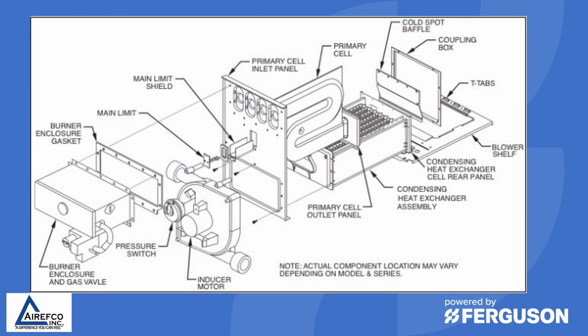When changing out a primary or a secondary heat exchanger on a gas furnace, you should have a complete breakdown of what all is involved in that primary and secondary heat exchanger. There are baffles that are in place to direct the air around the heat exchanger, and if these baffles are not replaced with the heat exchanger, there could be overheating issues.